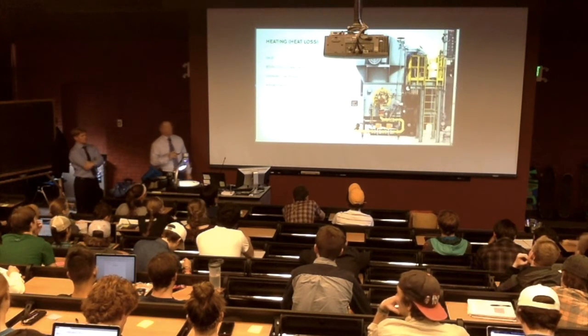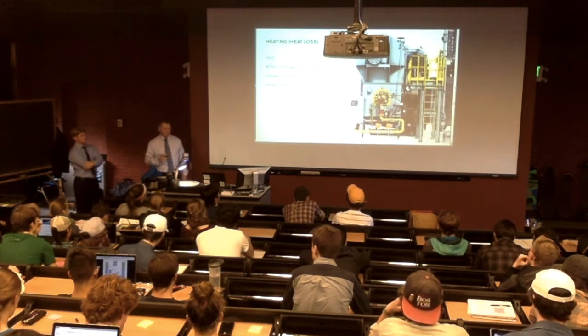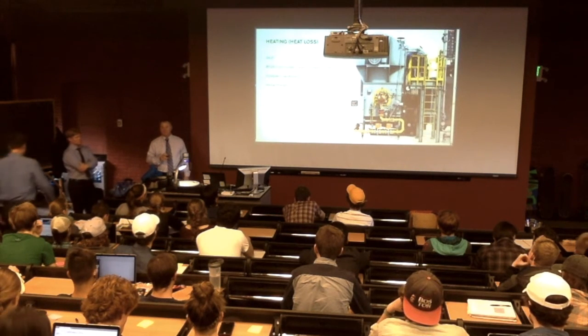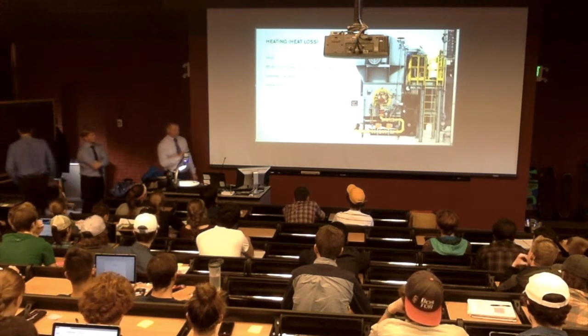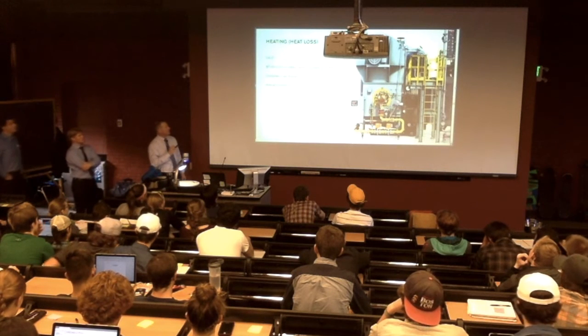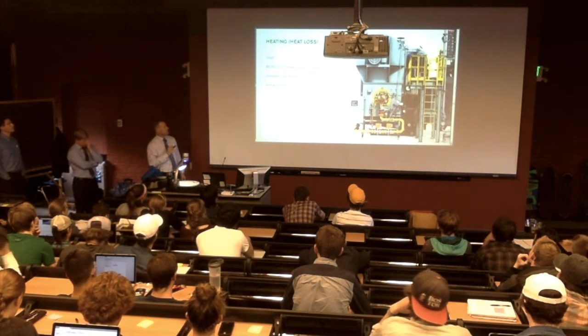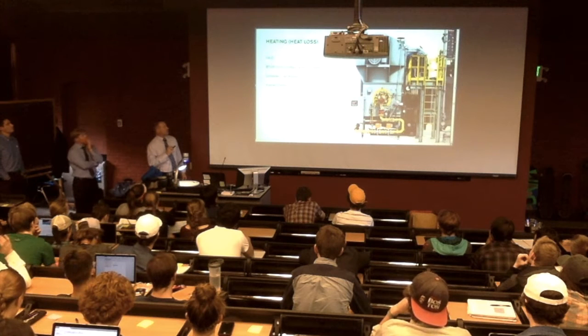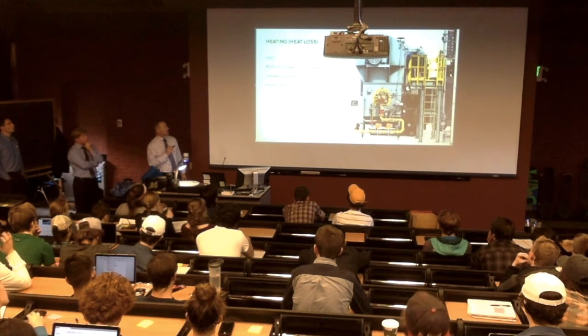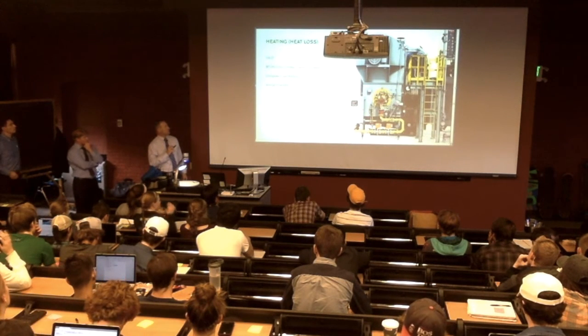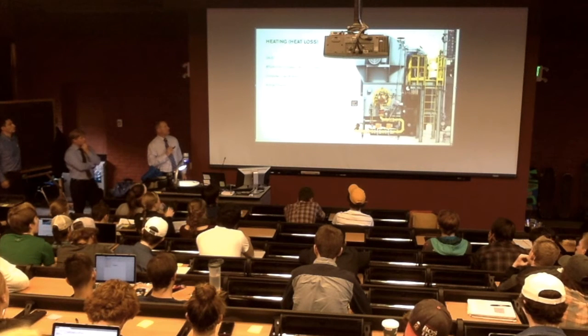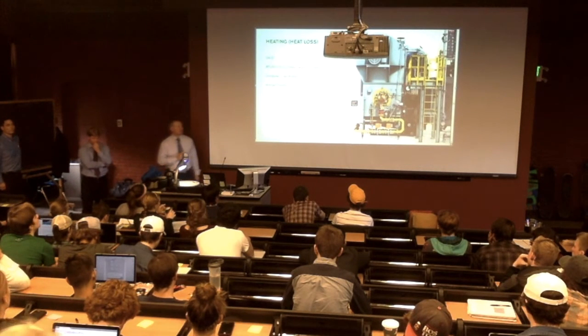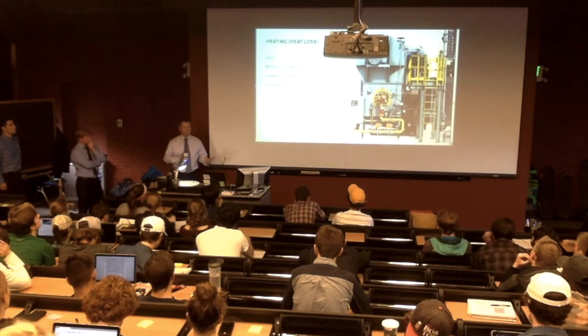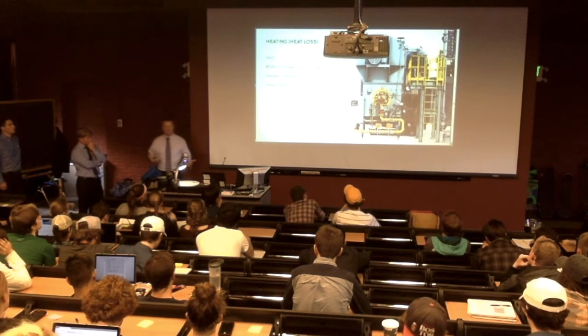Heat loss, if you take mechanical or mechanical and maybe chemical engineering, you'll learn this equation quite a bit. UA delta T. U is the U value of the thermal of the wall assembly or the assembly that it's going through. A is the area of the building, and delta T is the temperature differential. As I mentioned, the design temperature for Burlington, Vermont is 20 below zero.